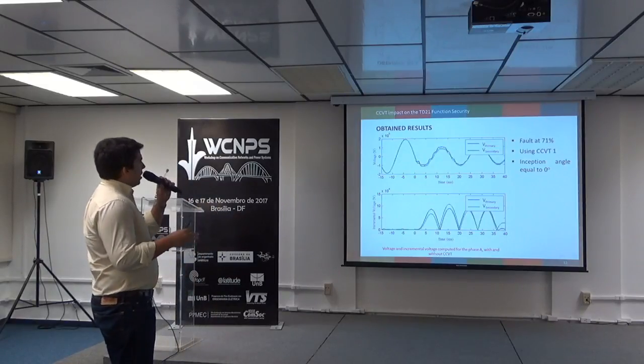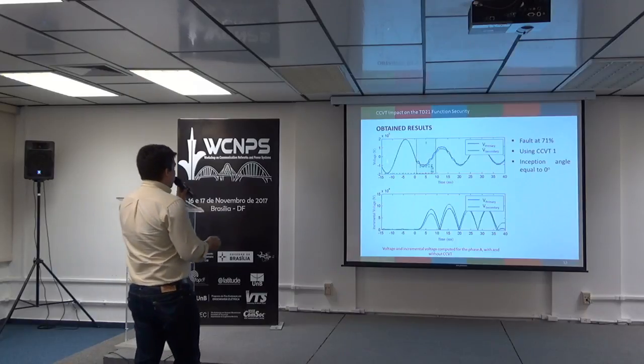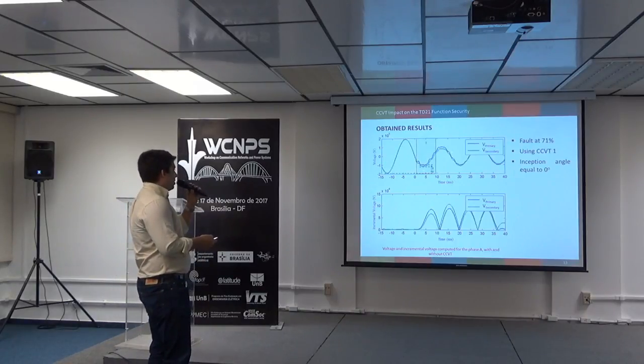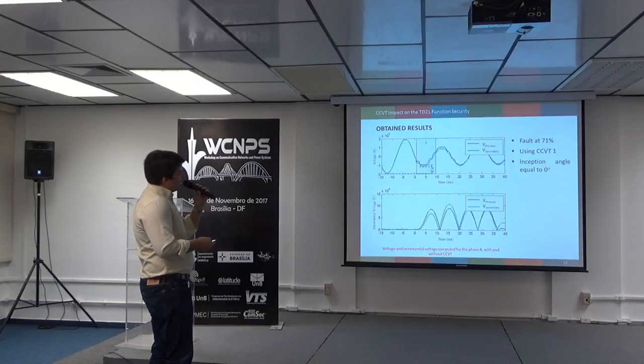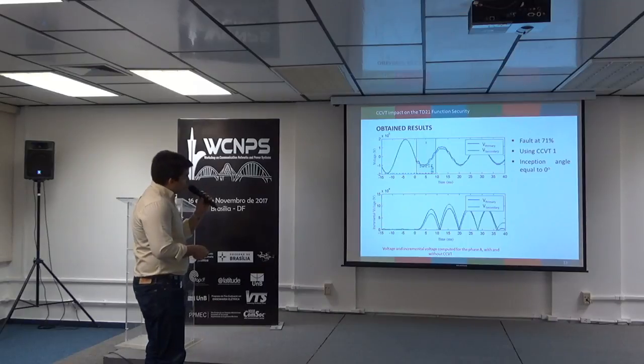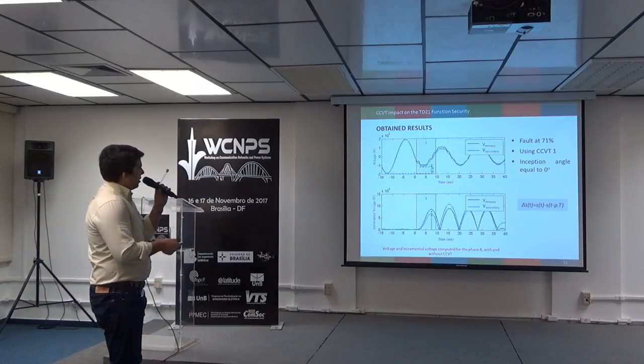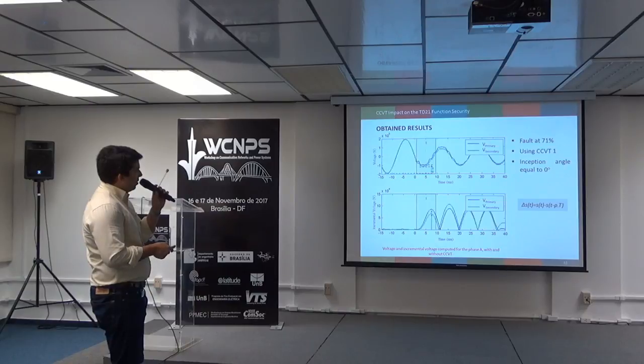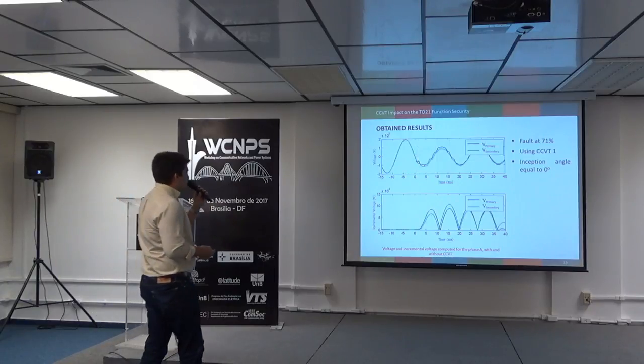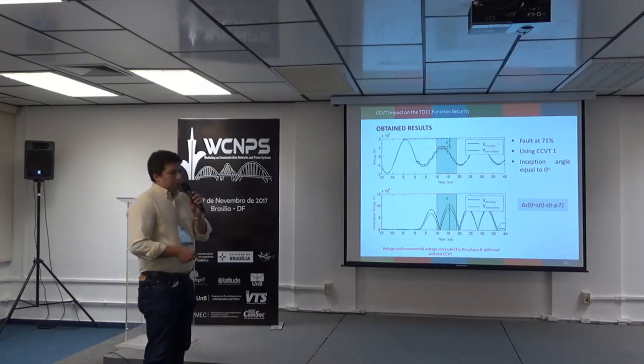Just to illustrate the cause of this problem, here we have the primary and secondary voltage. It's clear that there is a difference between both signals, and when we compute the incremental voltage, we have a difference in this first part of the signal, but it does not result in a misoperation of this function. But in the second part of this signal, we have a problem because the V secondary is greater than the V primary, so we operate improperly.